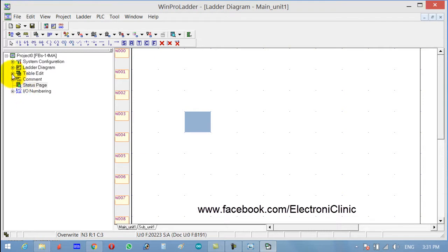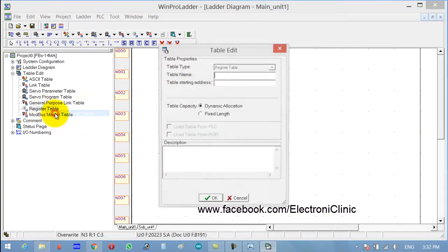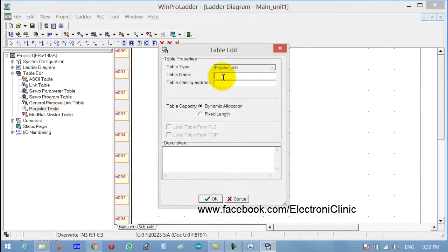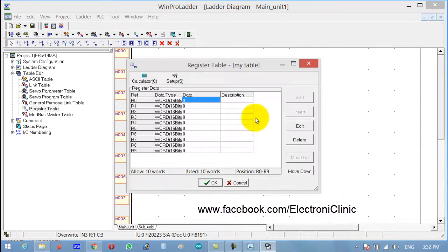Click on Table, Edit Register Table, right-click, Add Register Table. Set the table name to 'My Table' for example, table starting address R0, and fixed length. I need 10 registers, so R0 to R9 gives me 10 registers. Click OK.